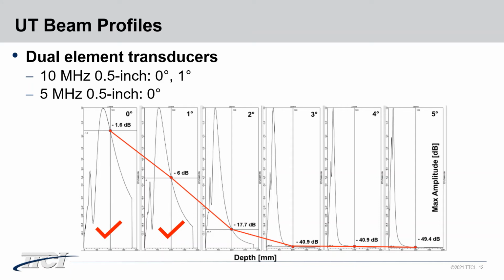However, when we reduced the transducer frequency to 5 MHz, only the transducer with 0 degree roof angle had acceptable results. Transducers with other frequencies and diameters did not have acceptable signal amplitude.